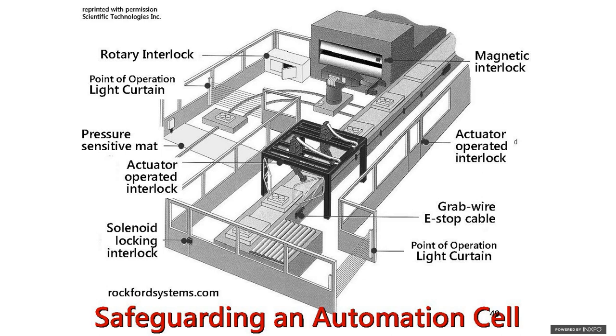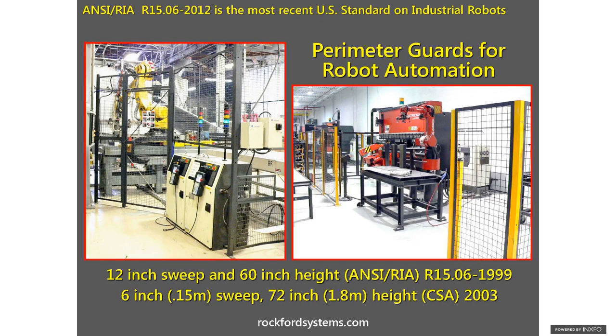Safeguarding an automation cell. Anything with robots in it usually requires a combination of safeguarding. There's a perimeter guard around this. There's a point of operation light curtain. There's grab wire cables. There's various types of interlock switches, all of which have to report back to some sort of input that accepts the safety inputs to tell you what needs to be reset. Machine's running along. All of a sudden it stops. You've got to figure out why and correct it.